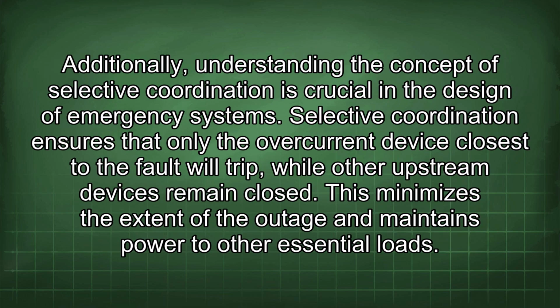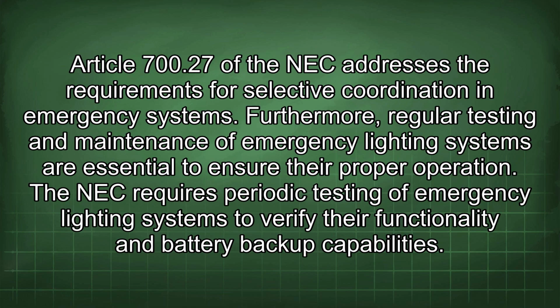Additionally, understanding the concept of selective coordination is crucial in the design of emergency systems. Selective coordination ensures that only the overcurrent device closest to the fault will trip, while other upstream devices remain closed. This minimizes the extent of the outage and maintains power to other essential loads. Article 700.27 of the NEC addresses the requirements for selective coordination in emergency systems.